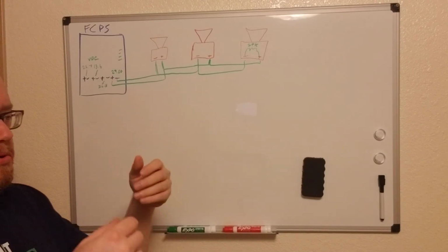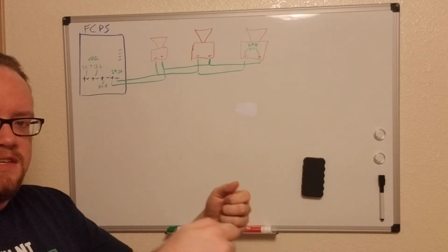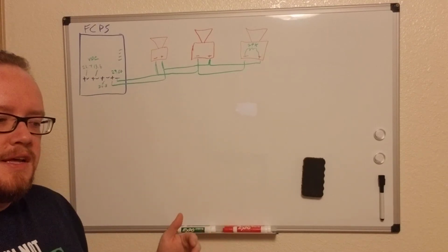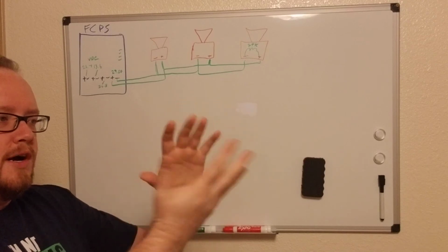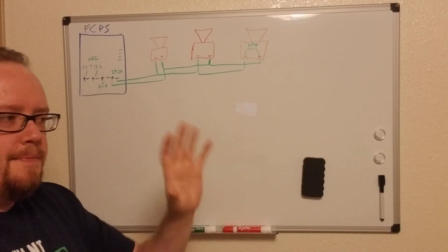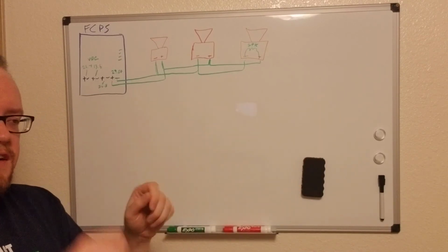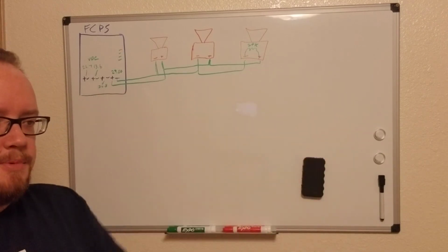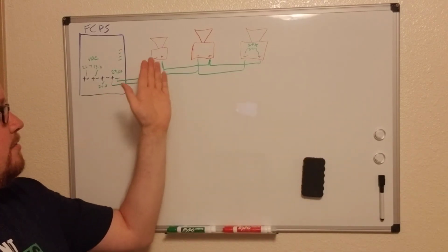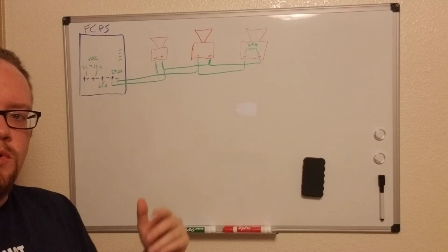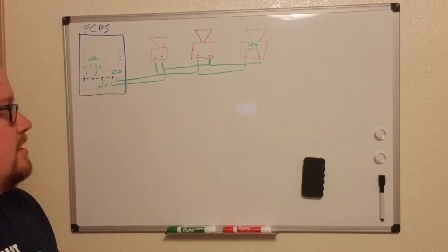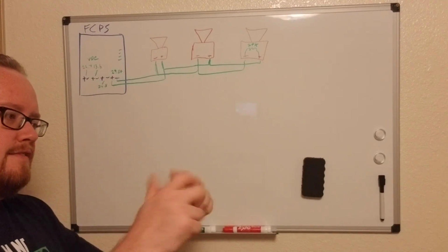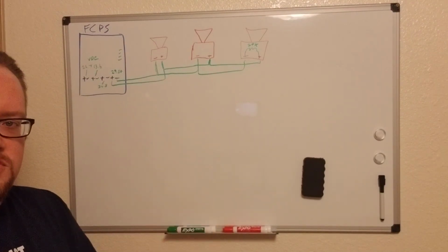But compared to checking for end-of-line resistance every single time, this is much faster, especially if you have horn strobe devices where the wires stay in a mounting plate and you're just popping the front of the face off. You can check it, snap it right back on. It takes you 20 seconds to figure out what circuit you're on, what the issue is, compared to 2 minutes to yank the wires off, meter them, stick them back in, re-terminate them.